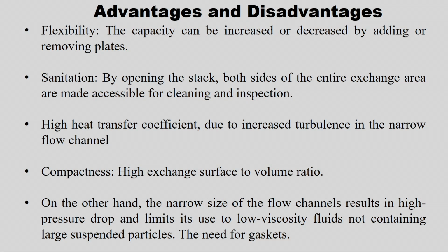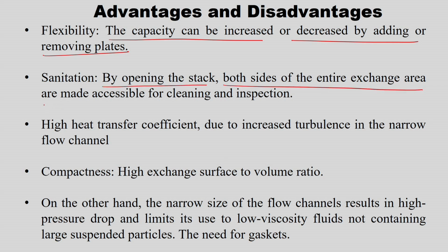So, advantage wise, the capacity can be increased or decreased by adding or removing plates, this I already discussed. So, that flexibility I have in the plate type heat exchanger. For sanitation, by opening the stack, both sides of the entire exchange area are made accessible for cleaning and inspection.